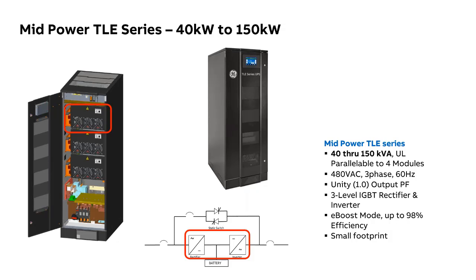So I have a couple of slides here, and this is just showing the ABB offering. There are three different product families in the ABB monolithic UPS offering. And actually, one of them, the mid-power TLE, is a legacy GE UPS; I noticed the GE logo on this one this morning. So just for illustration, that mid-power TLE UPS is based on a 50 kW power module. It's available from 40 kW to 150 kW, and the one we see on the right here will support 150 kW.